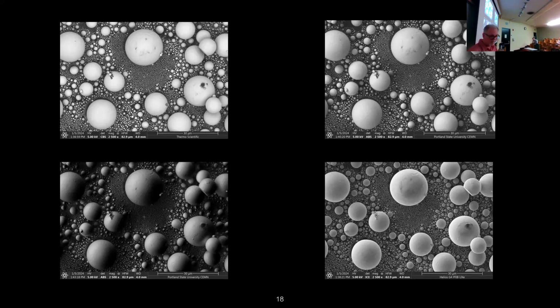And then the bottom right detector is a completely different detector. This detector is in chamber, but it's high angle in chamber. It's a secondary ion and electron detector. I forget what the ICE acronym stands for. I think it's ion conversion and electron detector. And in this case, we get some highlighting on this particular sample because if you look at the larger spheres in here, you can see it's very much whiter around the perimeter. And I think that has a nice effect.